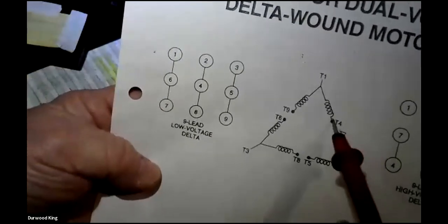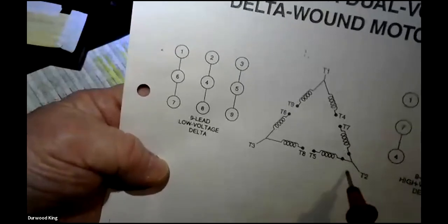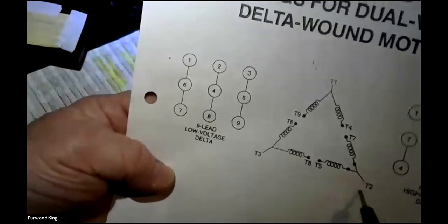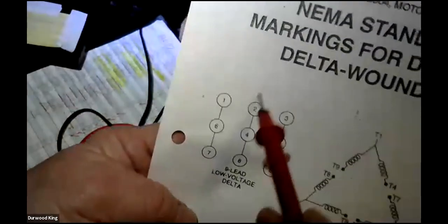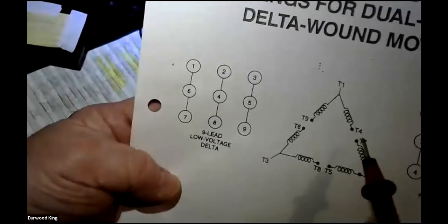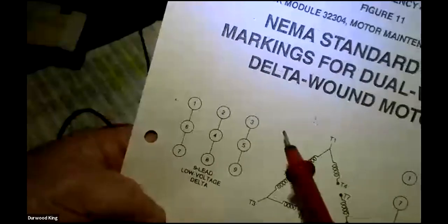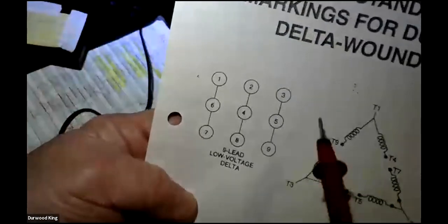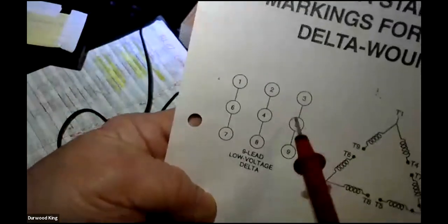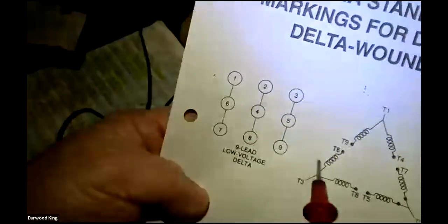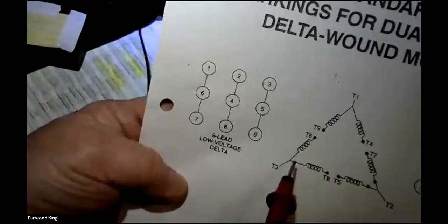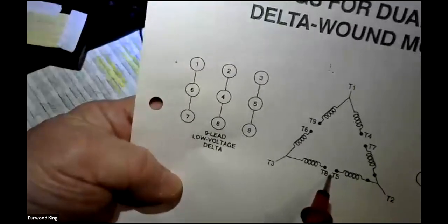So line 2 comes in, and then it hits 2 and 4 and 8. So it hits the bottom right of each set. 2, 4, the same phase, the same T2 phase hits 2, 4, and 8, and they're together, okay? And then the third leg coming in, it hits 3, 5, and 9 coming from the starter. So T3 comes in, hits 3, it hits 5, and it hits 9. So it hits the lower left here, lower left, and lower left.